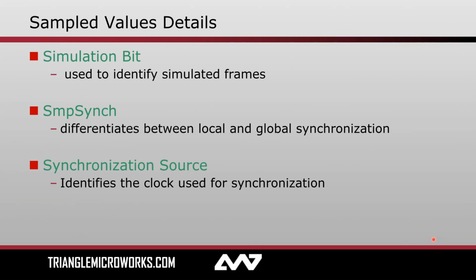So a couple more key considerations. The simulation bit is applicable to both GOOSE and sample values. It's a bit in the header of a GOOSE or sample value message that indicates if this particular stream is simulated or not. Matt talked a moment ago about the GOOSE publisher. In Test Suite Pro, it has the ability to publish simulated streams, although you as the end user can choose to turn that off and pretend it's not a simulated stream and it's a real stream coming from an actual device. SMP sync and synchronization source.